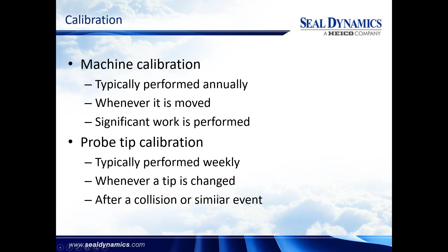And of course, too, should you have a crash? I think everybody who's got a CMM, we've all done it. We've all crashed and broken a tip once or twice, maybe even three times. But anyways, depending on how long you've been working with CMMs, it's an inevitable event. We make mistakes. So obviously, after you have a collision or a similar event of that nature, you need to do a probe tip calibration.